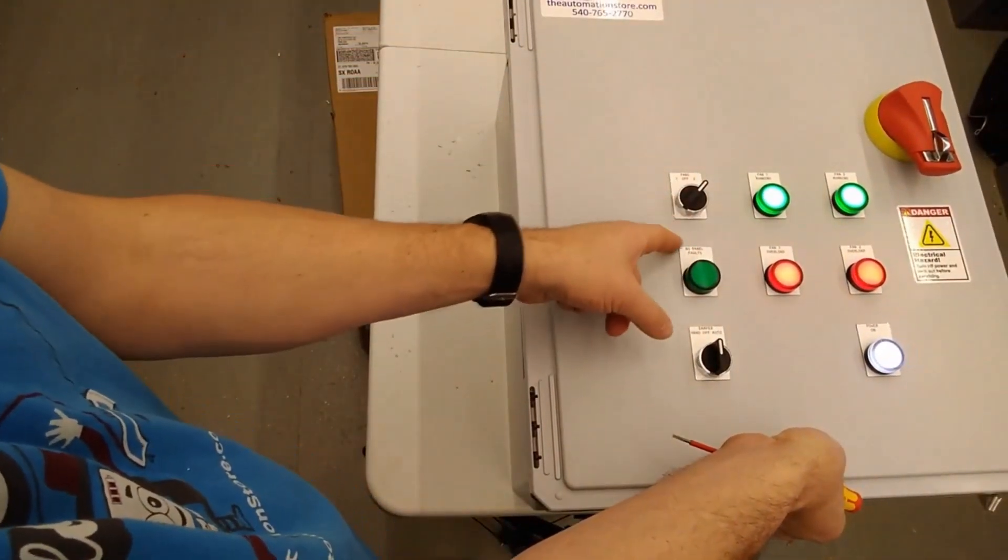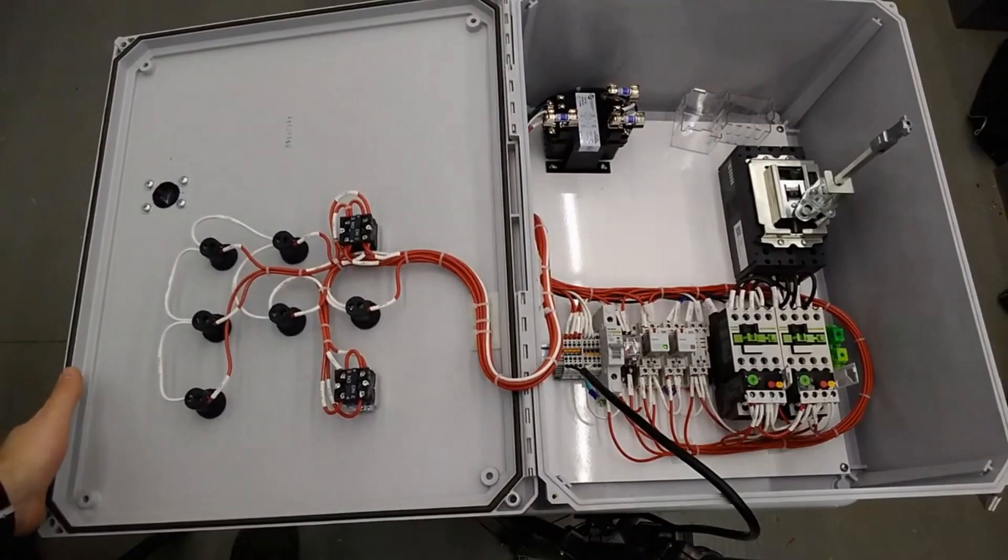I didn't note there but in all those situations you'll see the panel fault light went out which corresponds with this relay dropping out which breaks the continuity of that circuit.